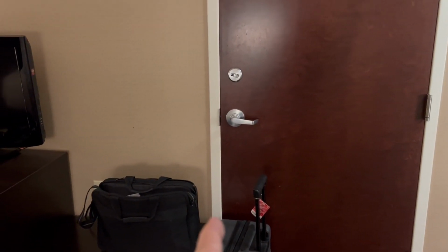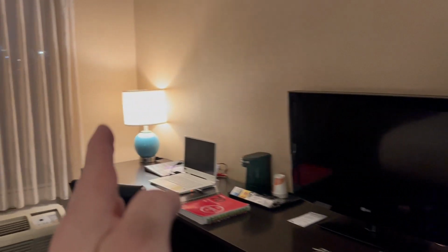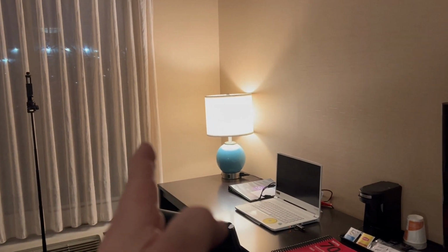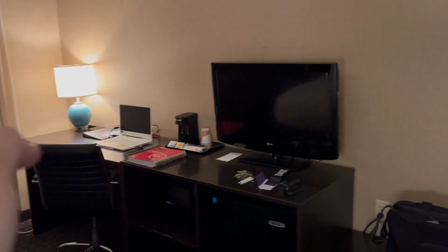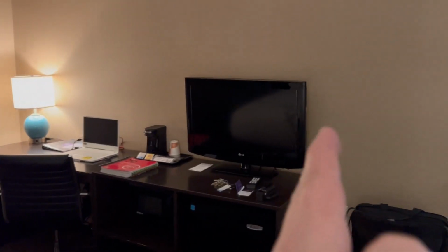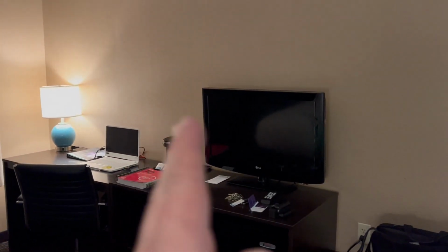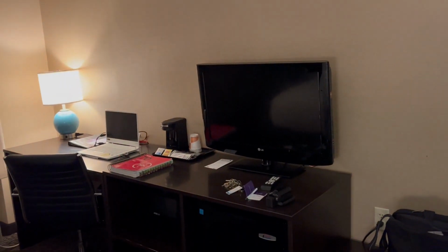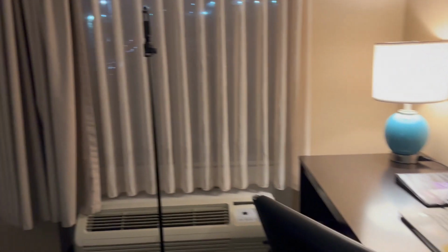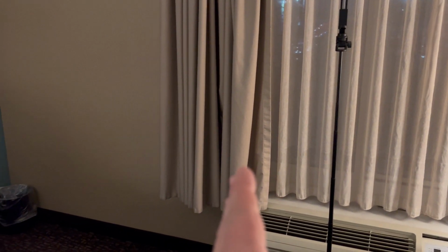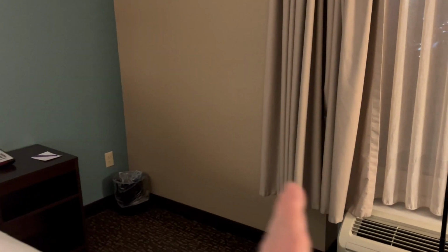Here we have another door, and let's go out 6 feet, which is about here someplace. Then let's look over here where the window is, and let's go around that little corner, and I would say another receptacle outlet right about here. So for this wall, it looks like we can get away with maybe 2 receptacle outlets. I've got 1 over here, the second one, and the third one. So far I've got 3 receptacle outlets. I'm going to start from the window and go out 6 feet. With that receptacle outlet, that's within 6 feet of that corner.